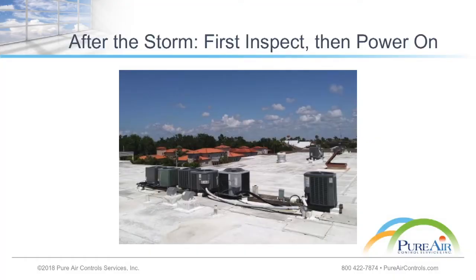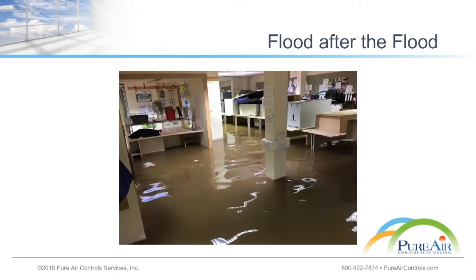But that's way too reactive. Basically, you should rinse and repeat what you did before the storm - get up and do your visual inspection before power is restored, make sure there's no damage up there. I've seen a very large facility that, after a tropical storm came through, had almost every drain line on their roof destroyed. They were in a hurry and turned all their units back on, so they ended up with a disaster after the disaster - the entire facility was flooded just from condensate from the air conditioning systems, which is easily avoided with a post-storm inspection.